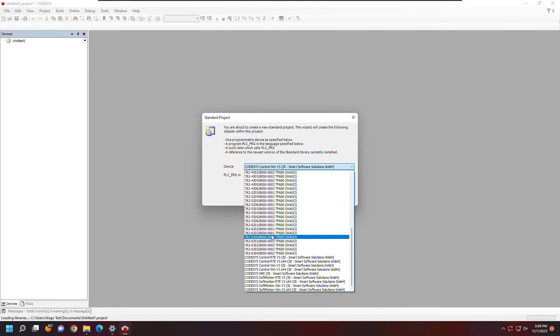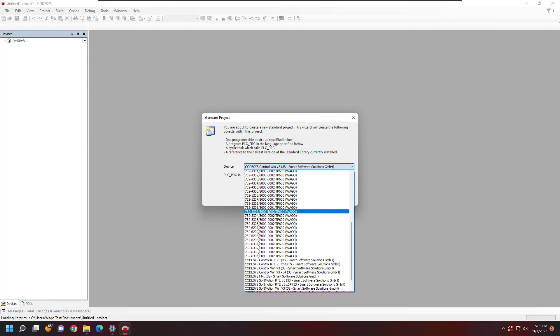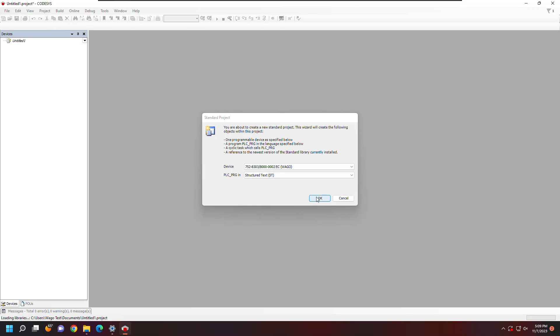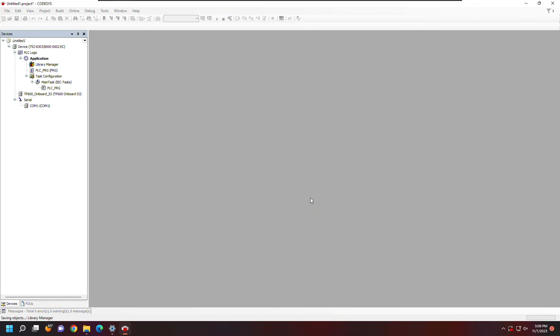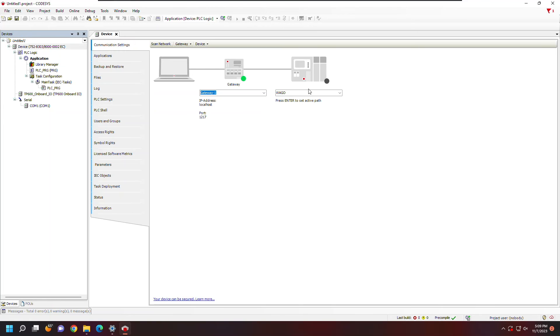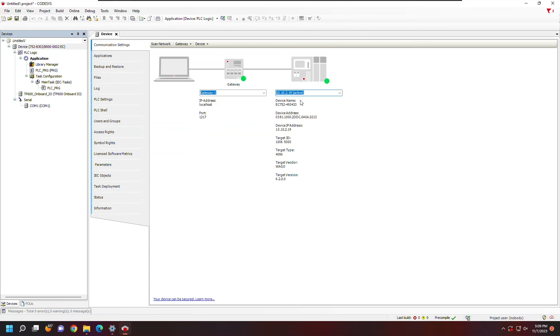Now I can select my WAGO device from the dropdown. Here I'm just going to search for the touch panel model number that I have. With my project now open, I can double-click the device on the left-hand side of the device tree. That's going to open up the communication settings, and I can enter the IP address of the device. After hitting enter, I should see the green light showing that I'm now connected to the device and ready to program.